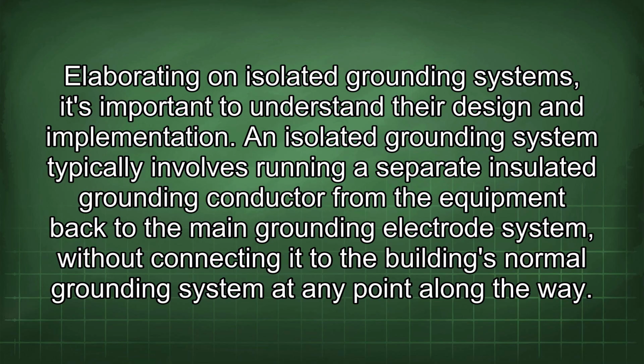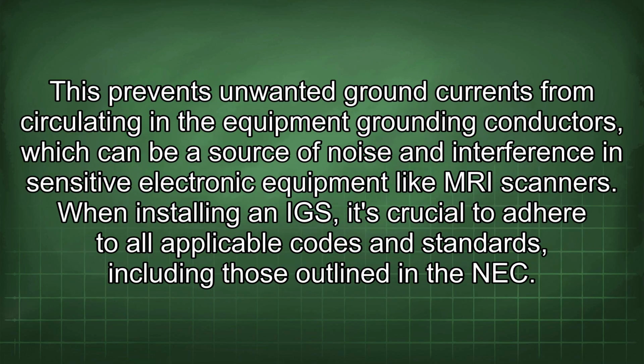Elaborating on isolated grounding systems, it's important to understand their design and implementation. An isolated grounding system typically involves running a separate insulated grounding conductor from the equipment back to the main grounding electrode system without connecting it to the building's normal grounding system at any point along the way. This prevents unwanted ground currents from circulating in the equipment grounding conductors, which can be a source of noise and interference in sensitive electronic equipment like MRI scanners.